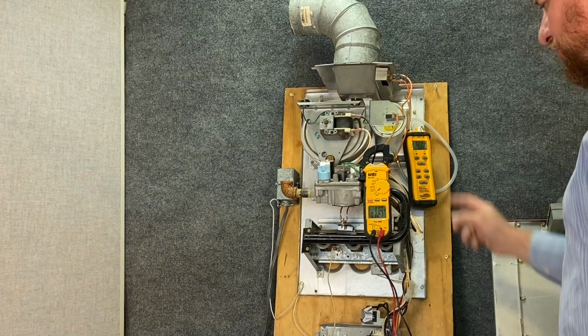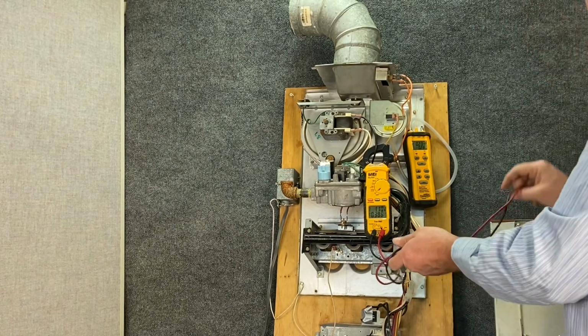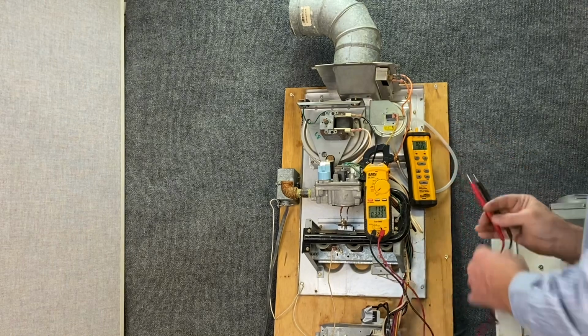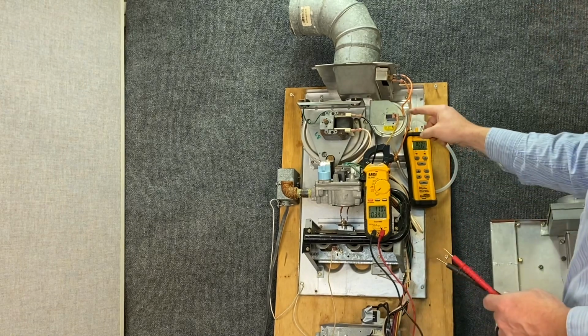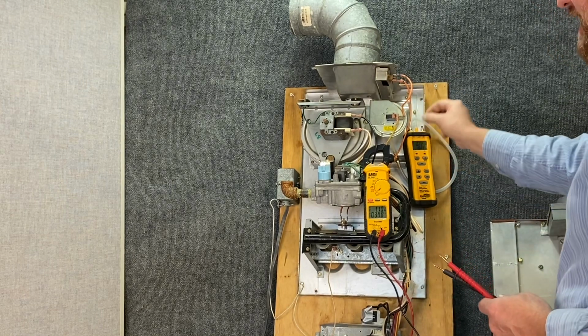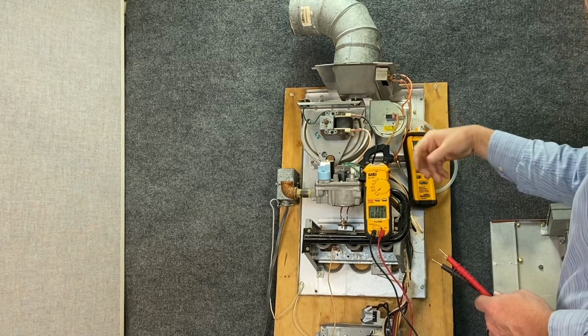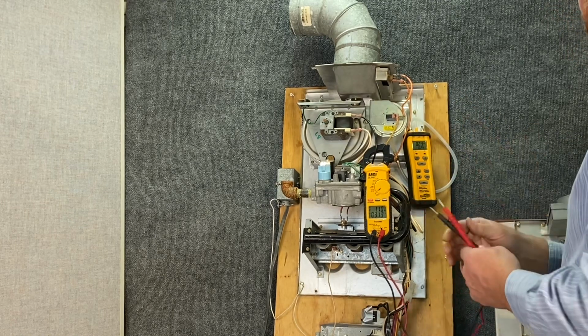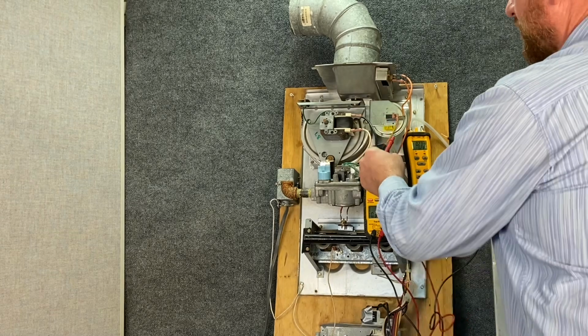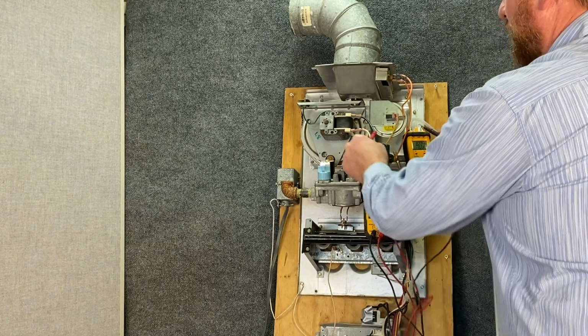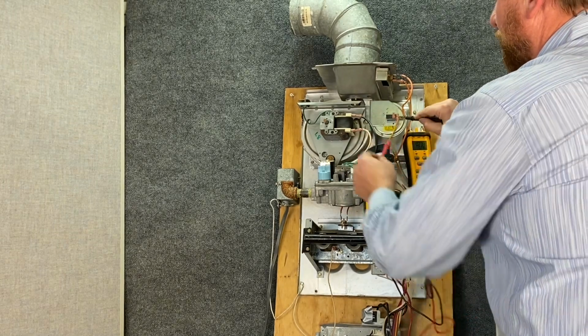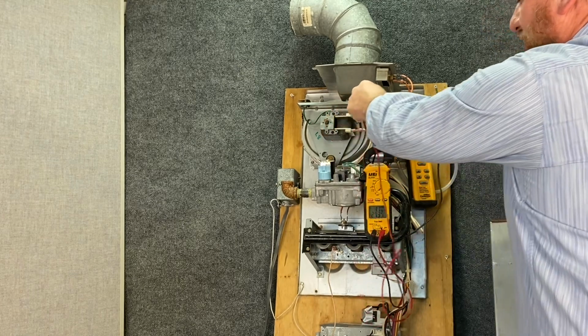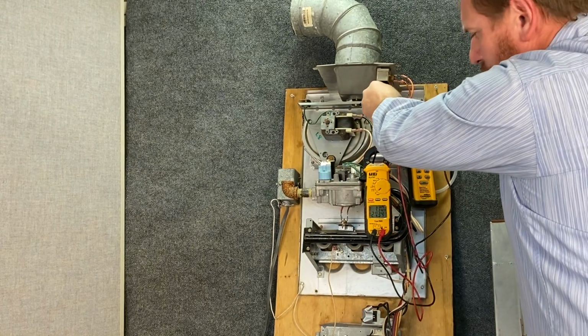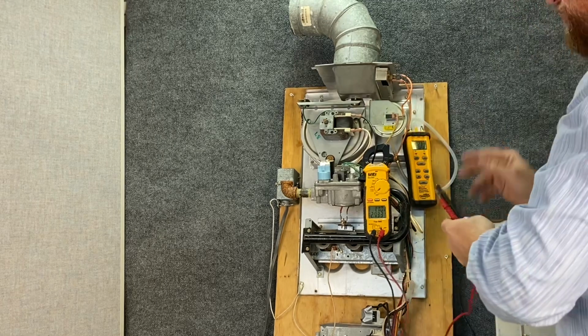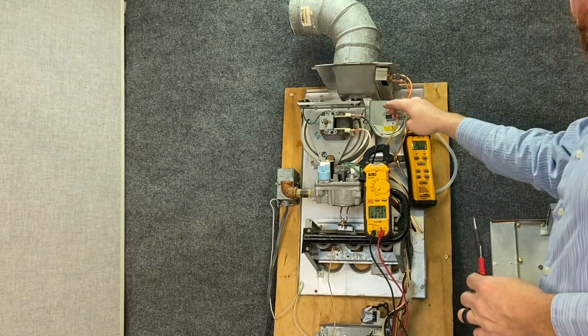So another thing we can do for the pressure switch to ensure that it's opening or not is check voltage. If I read 0 volts, the switch is closed. If I read any voltage at all, the switch is open. There's the potential for flow, but it's not flowing. So I have my meter on volts, the bottom number will read volts, the meter on one side and the other, it doesn't matter which direction, and I'm reading 27 volts. So because I'm reading voltage, my switch is open.